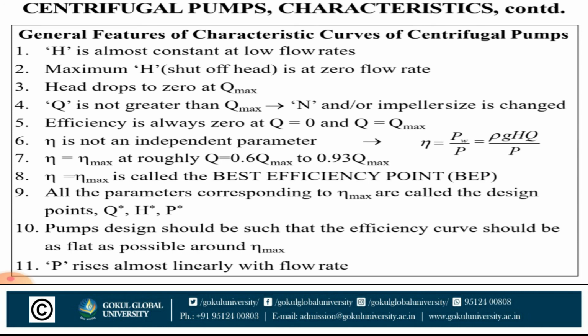Efficiency reaches its maximum roughly at discharge equal to 0.6 to 0.93 of the maximum discharge. Maximum efficiency is called the best efficiency point, or BEP. All the parameters corresponding to maximum efficiency are called the design point: Q, H, P.